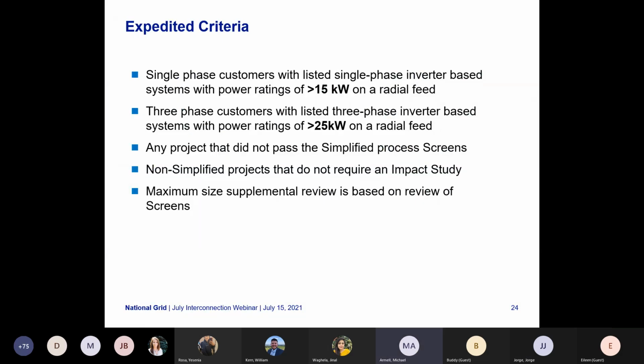So our expedited criteria, basically following along on what Jesse had said with the simple cases, we're on the other side of that. A single phase customer with a listed single phase inverter based system with a power rating greater than 15 kW on a radial feed would go into expedited, as well as three phase systems greater than 25 kW on the radial feed.